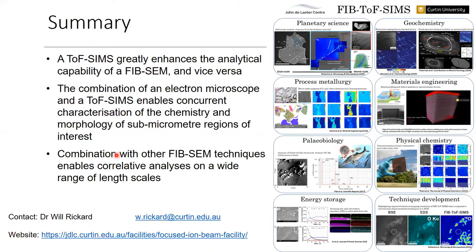On the dimension of measurable regions: the analysis area corresponds to where you scan the FIB beam, but you need a sufficient pixel size matching the probe spot size and adequate current density for a good signal-to-noise ratio. Typically we work at 50 microns by 50 microns or less, up to perhaps 100 microns by 100 microns. At larger field of view you're often better off using EDS. To take advantage of high resolution, smaller fields of view — 20 microns by 20 microns down to 1 micron by 1 micron — are preferred.